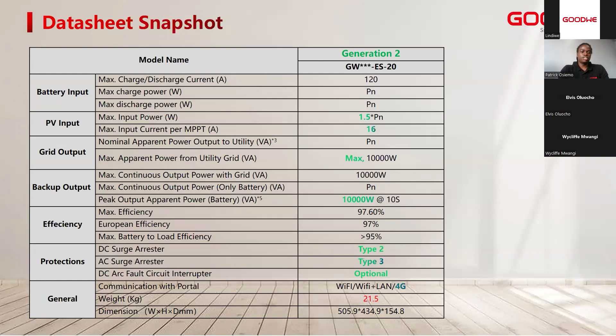And we do take note of the safety features for the installation of your PV modules. Thus the inverter comes ready with integrated type 2 SPD surge protection devices for the DC side, and on the AC side, you get integrated type 3 SPDs. The inverter communicates through various modes: Wi-Fi, LAN, and 4G. All these are just to increase the flexibility in which you can commission or monitor the inverter itself. It's quite lightweight and compact, so 21 kg should not be that heavy for most installers. So it's quite easy to do a wall mounting installation.